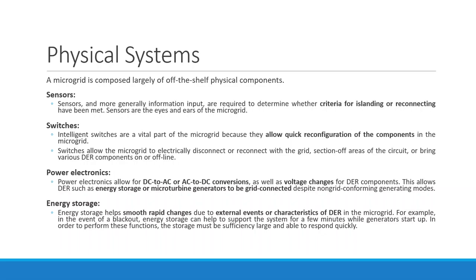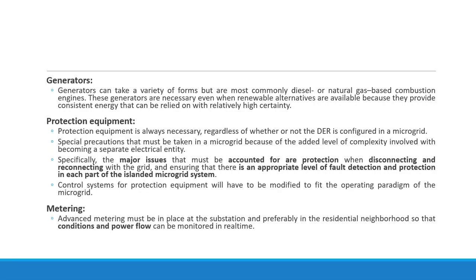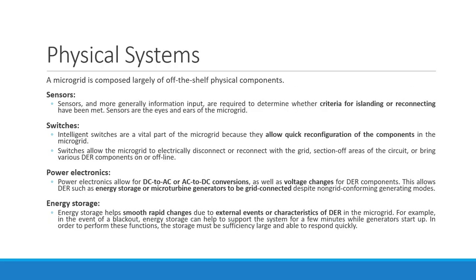The physical system in a microgrid can be largely composed of physical components. It could be sensors, switches, power electronics, energy storage devices, generators, protection equipment, metering devices. So broadly, if you think about what it could consist of, first it is the sensors. Why are the sensors needed? Sensors, you could say more generally, provide information input required to determine whether the criteria for islanding or reconnecting are met and that should be done.